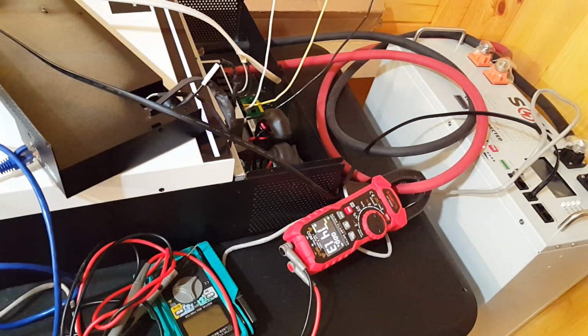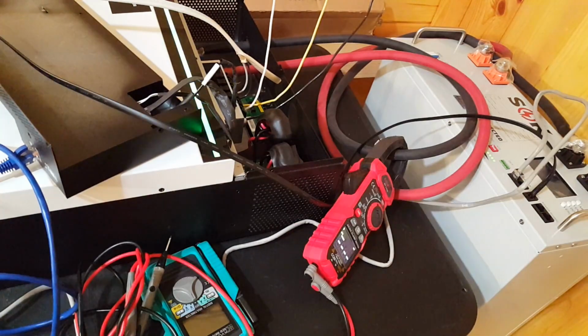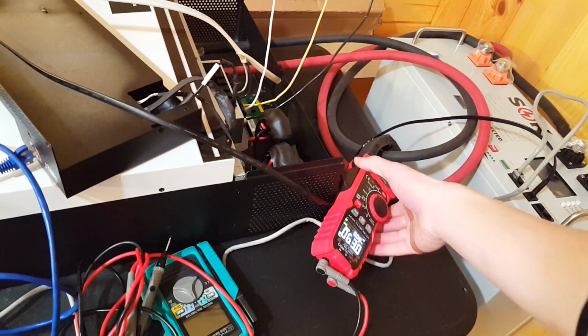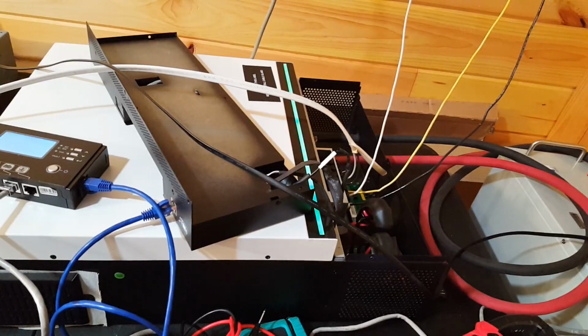You know, it is a really crazy surge. I don't expect it to start the table saw every single time, but at the very least, it should be able to do the grinder and the compressor without a problem. We'll try a few more times, and then the next thing we'll do is combination of different loads. We'll go back to the shop vac, which has a lower surge, and then we'll pair that with a space heater. Attempt number 4 with the table saw. Will it start? No. Amps on that try was 63. 1 out of 4. Battery has reset.